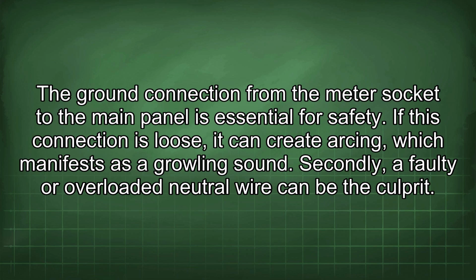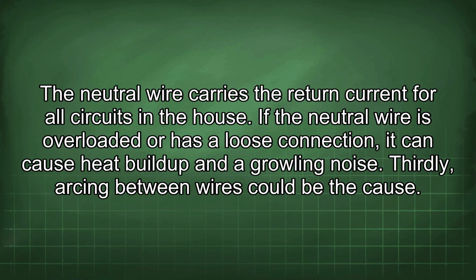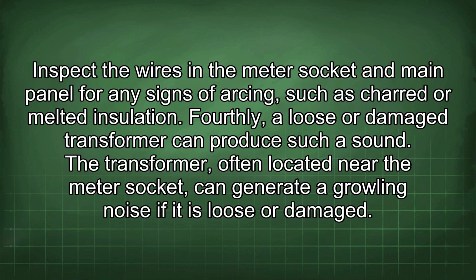Secondly, a faulty or overloaded neutral wire can be the culprit. The neutral wire carries the return current for all circuits in the house. If the neutral wire is overloaded or has a loose connection, it can cause heat buildup and a growling noise. Thirdly, arcing between wires could be the cause.